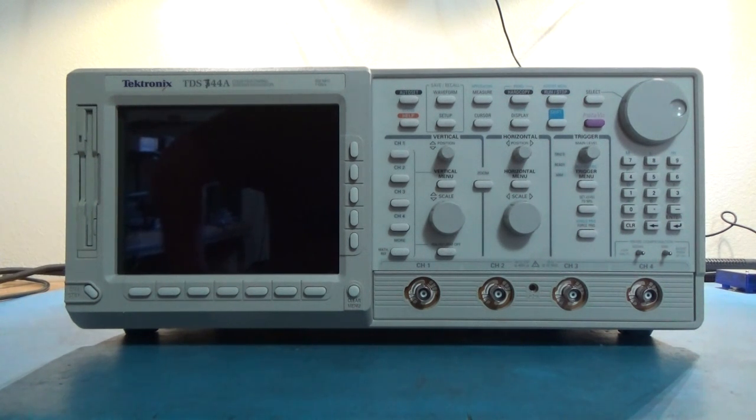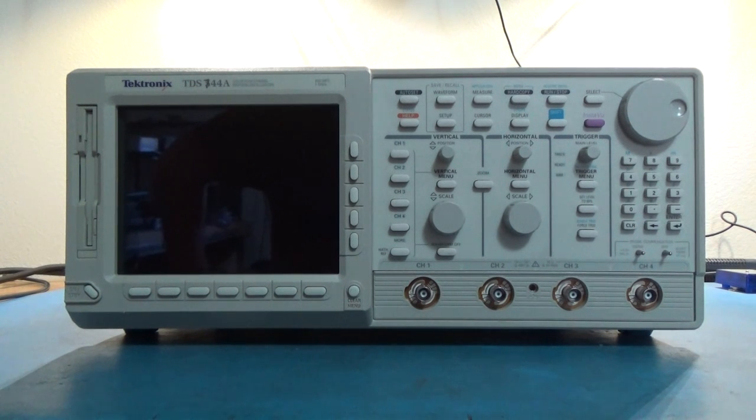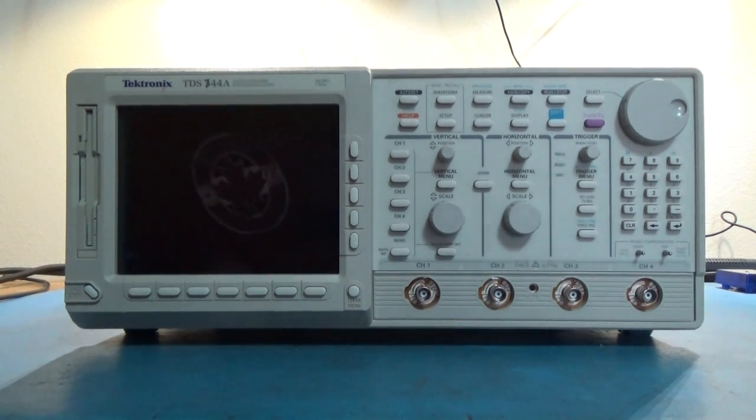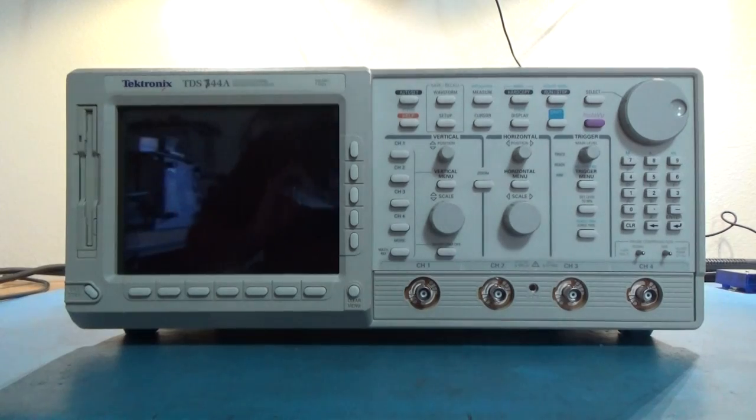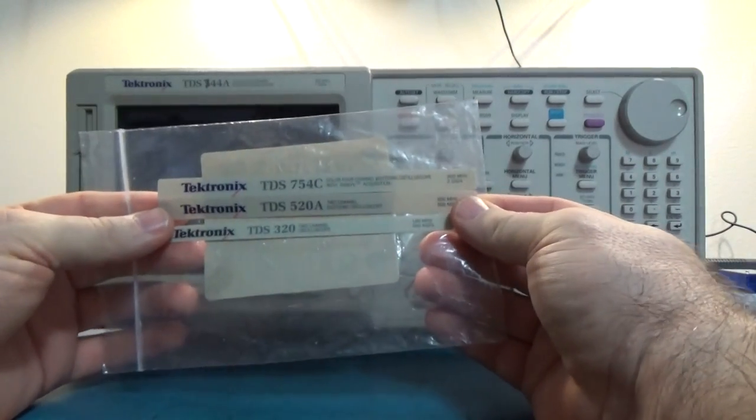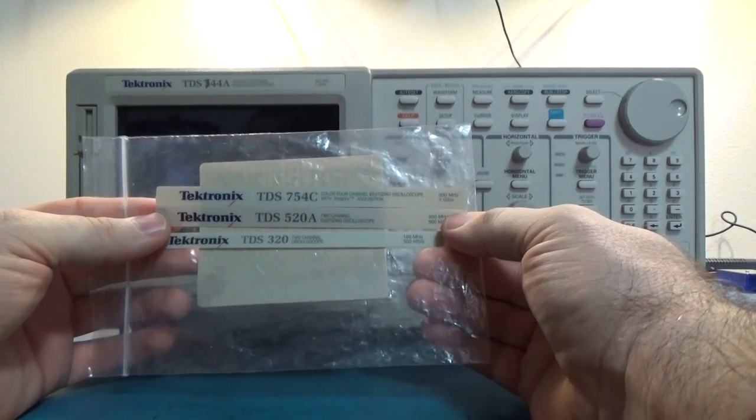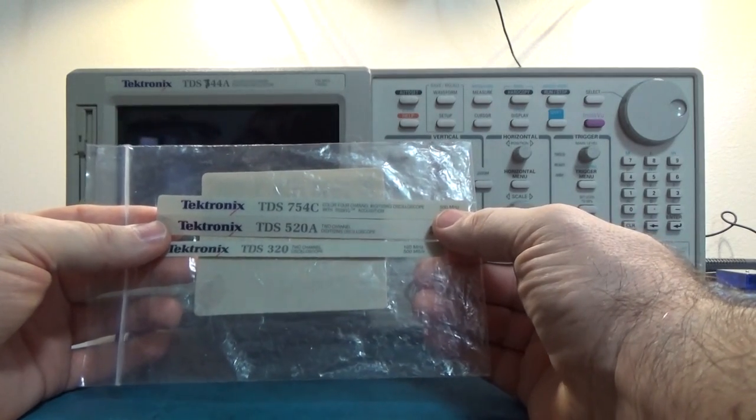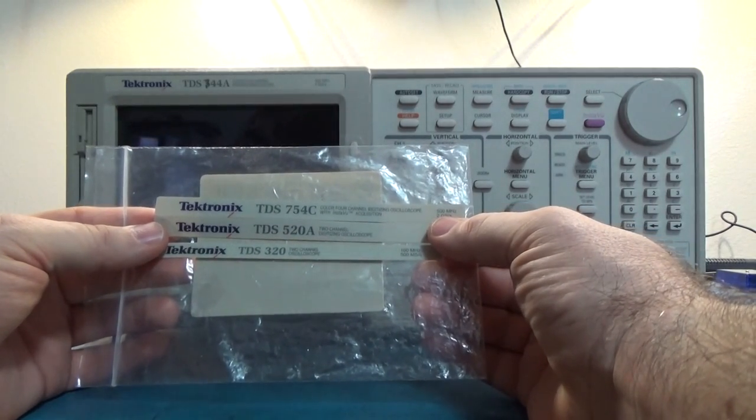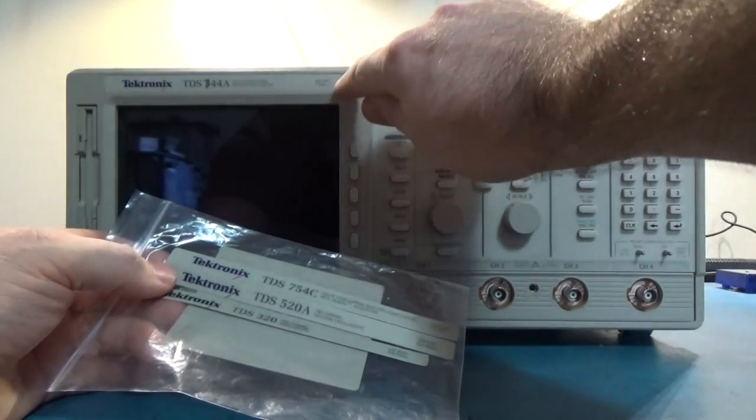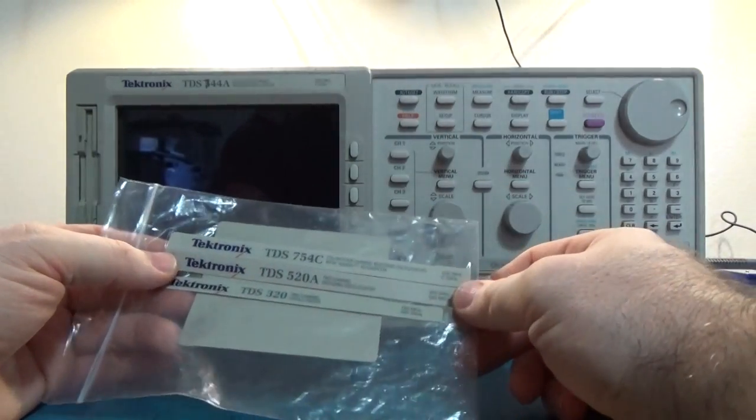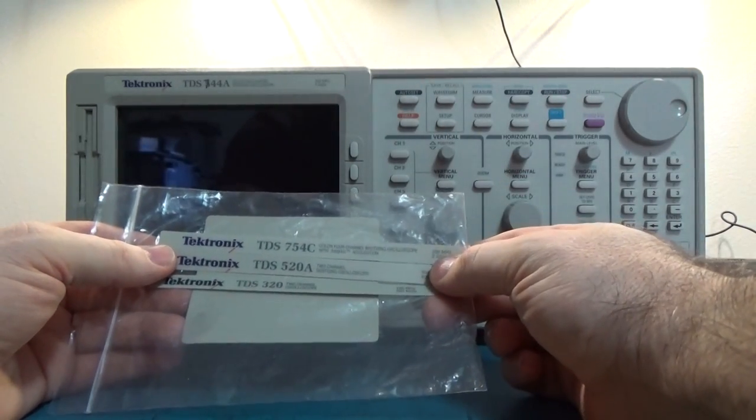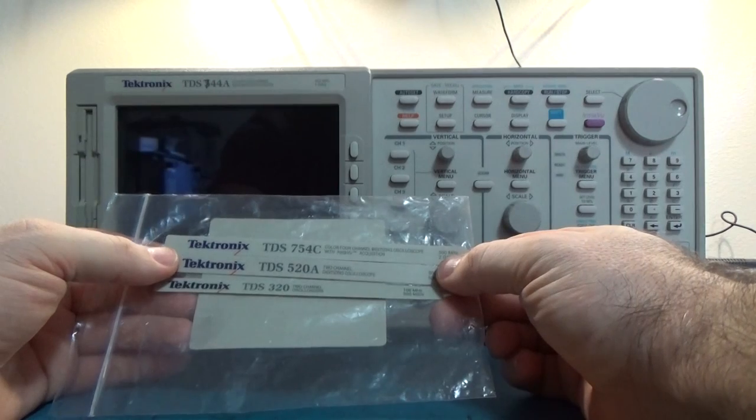This model came out in 1995 or so, and it was one of the first scopes that had InstaVu. The nameplate should be more similar to this nameplate, the 754C. It actually has 500 megahertz bandwidth and 2.5 gigasamples, unlike here where it says two gigasamples.